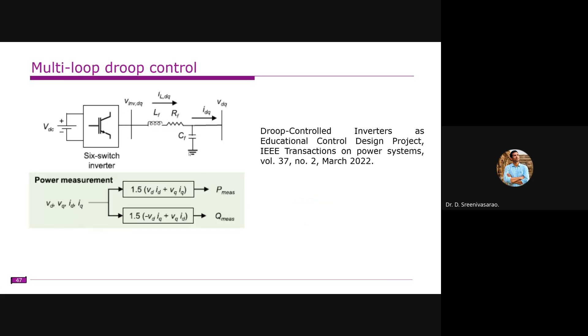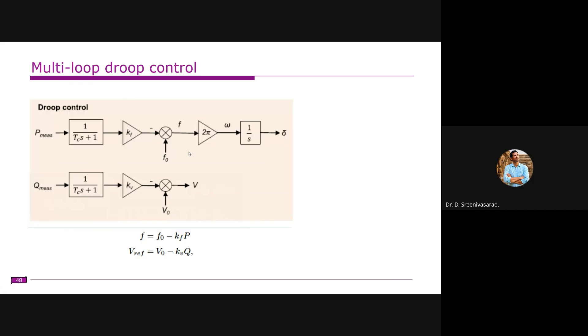Depending on the number of inverters, droop control may be needed for decentralized control. For simplicity, we consider only one inverter, so the droop portion is no longer required. The two important loops are: the power synchronization loop, which sets the phase angle based on active power, and the excitation loop, which adjusts the voltage magnitude based on reactive power.